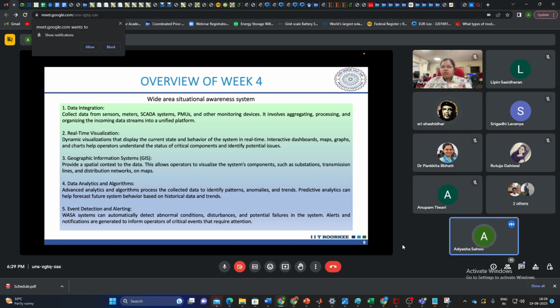Only in the RLDC centers and the NLDC center. These are the control centers for India, we can say. So these are responsible: if an action is needed in the northern region, the RLDC of the north region will get some alert on its screen, let's say that some line is getting overloaded. They will then feed this overload situation to the codes they already have.